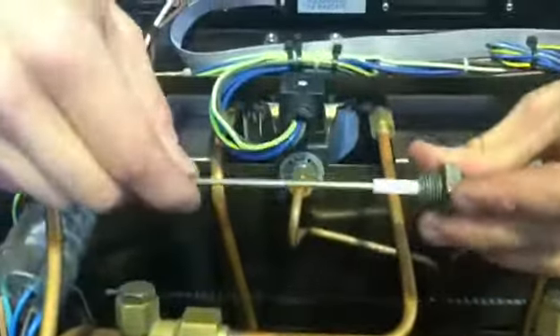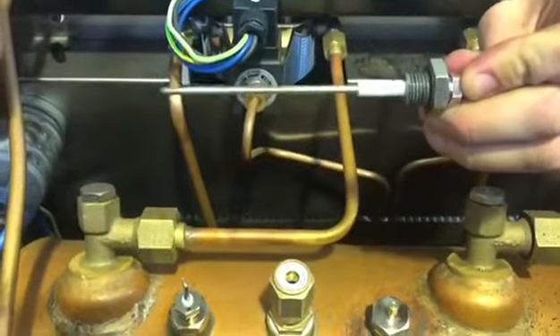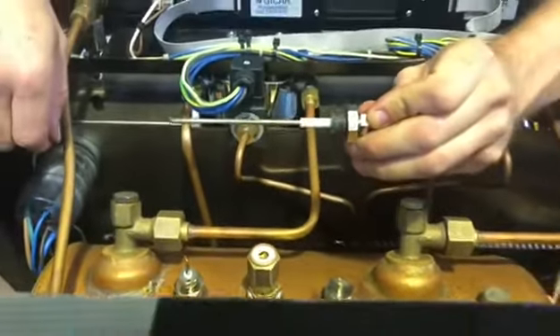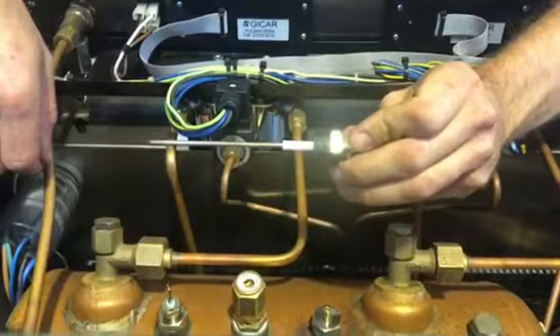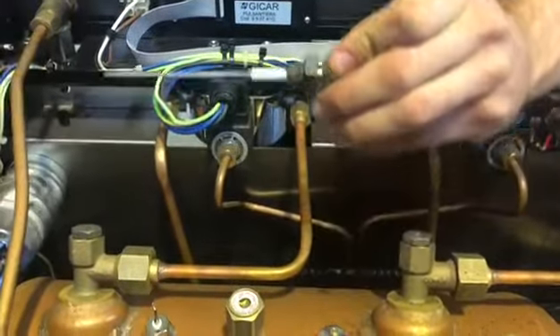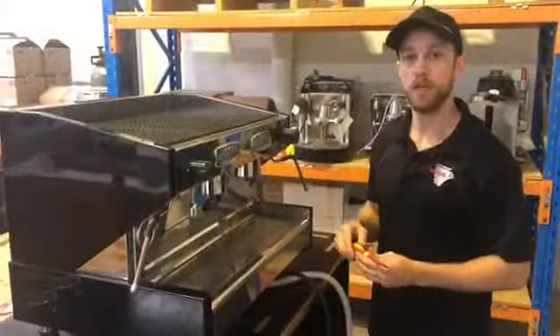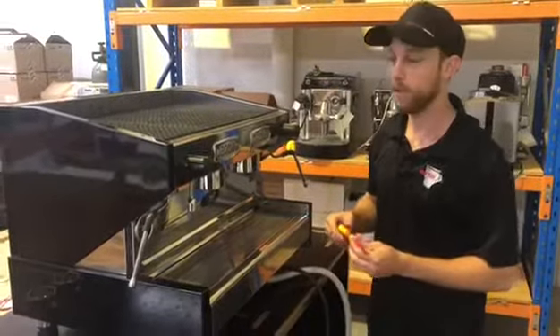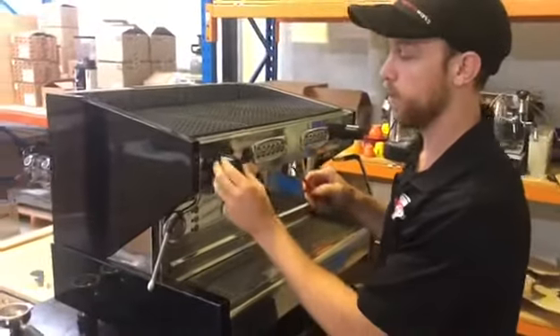Prior to installing the level probe, it's important to make sure that the length of the probe matches the new one. If it needs snipping, just use a pair of pliers to snip it to length.